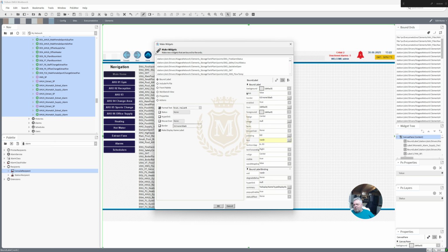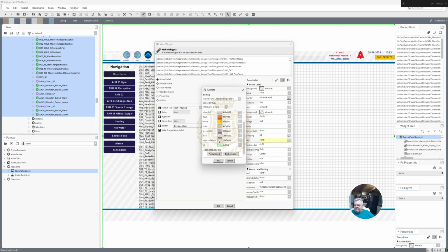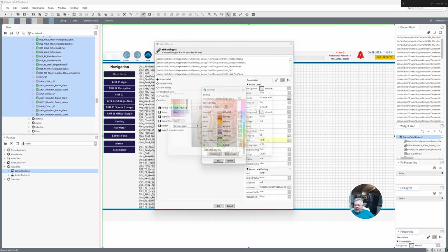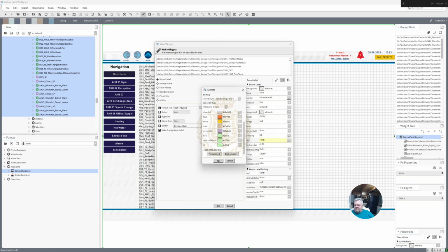I'm just going to show you how I bring them in, all my points. I mean, I've got to work on them all. So the background, I animate, so I right click that, animate it, and I status to simple, and I go background there. Because I have histories on all my points, I am actually going to put this very light green as a colour, and anything that's light green on my points means that there's a history attached to it and they can click on it and do a pop-up.